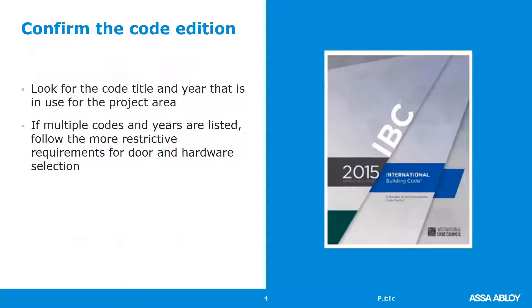The building code is adopted into law either by your city, state, or jurisdiction. The life safety plan should list the code title and the year applicable for the project. You may have multiple codes listed, especially if it's healthcare — a lot of times in hospital work you'll have more than one code, including NFPA 101. If you have more than one code, you have to follow the more restrictive requirements when it comes to selecting doors, hardware, and their applicable requirements.